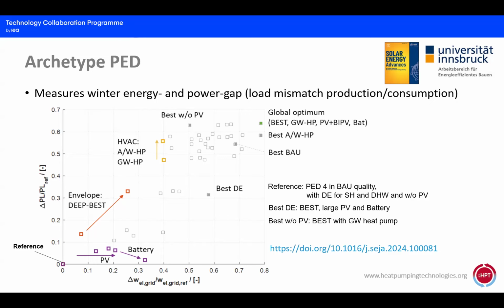You see if you increase your PV, then you can basically overcome the energy taken from the grid compared to the reference—the relative reduction of energy from the grid. With battery, you can further increase it, but you see that the peak load is not much reduced. That's why the PV will not deliver too much energy in wintertime, so this energy will be used, but you cannot really reduce your load peaks, or just moderately reduce them.